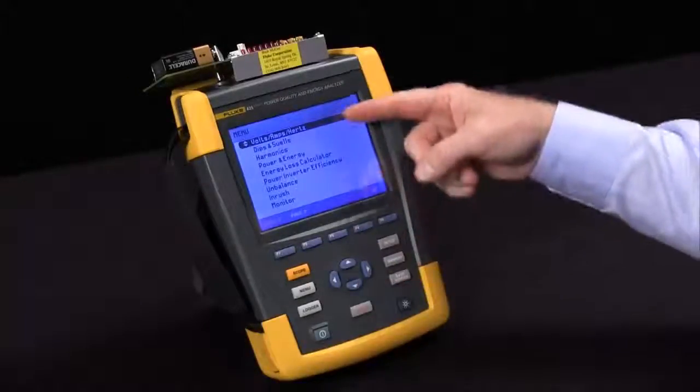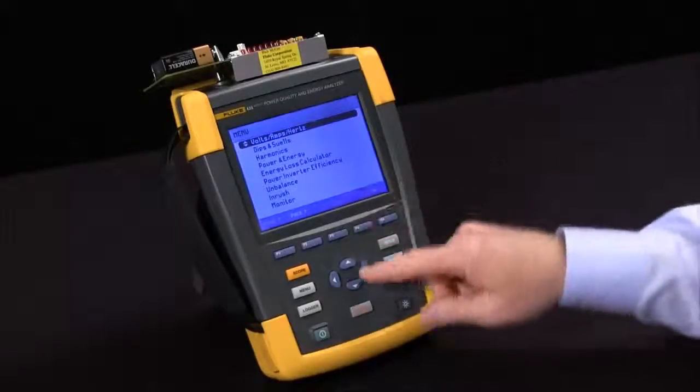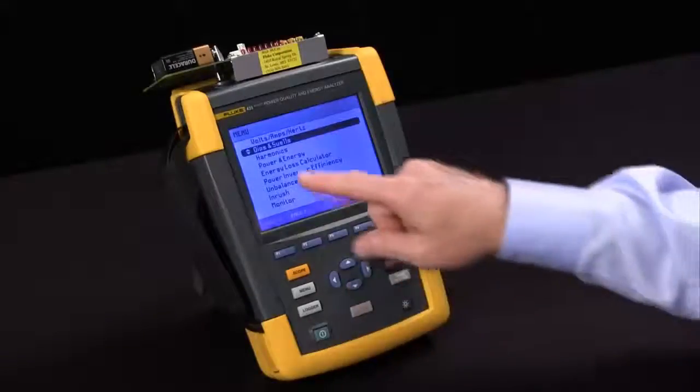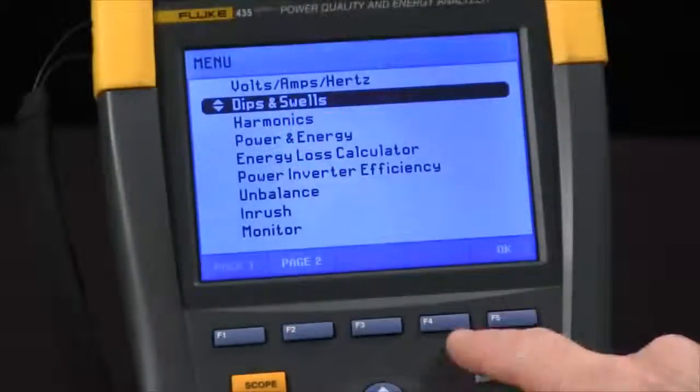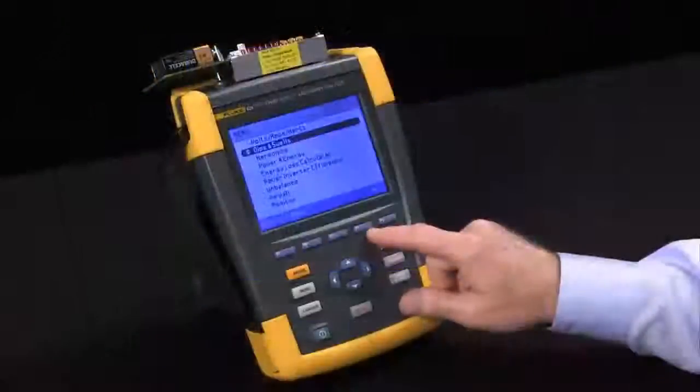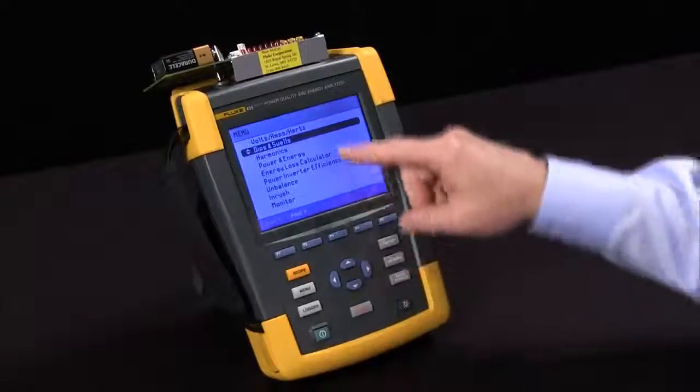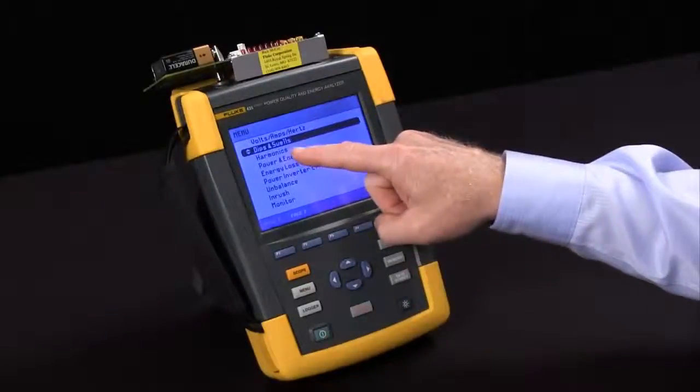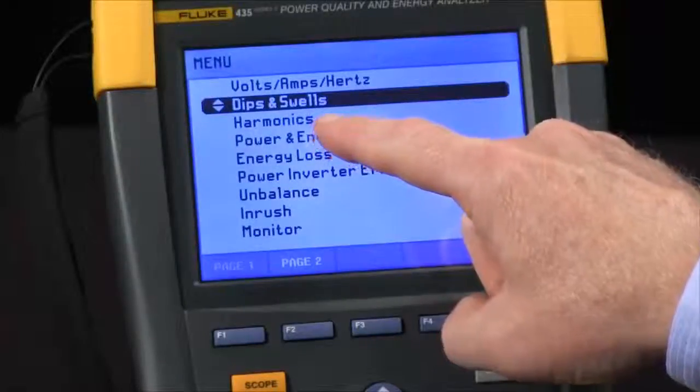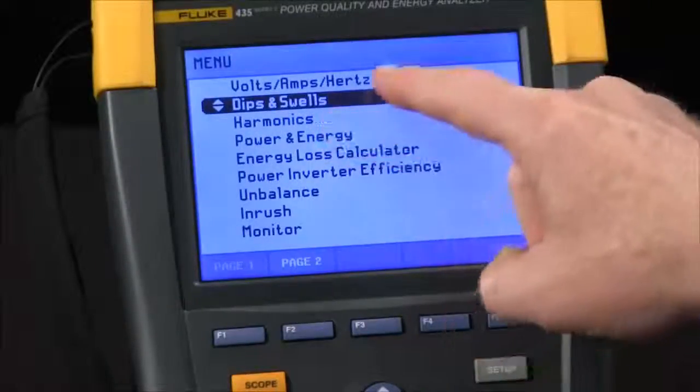The 435 trends for all of these tests at a rate of five readings per second. With the exception of dips and swells, we do 120 readings per second to give you half cycle resolution. We will see a lot more information recorded though in a harmonics recording versus volts, amps, hertz.